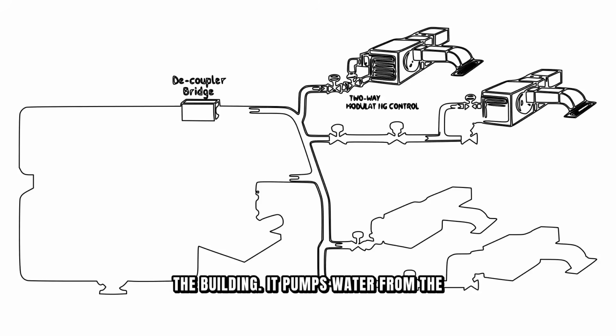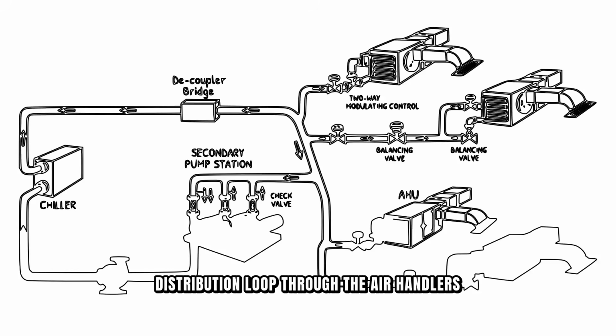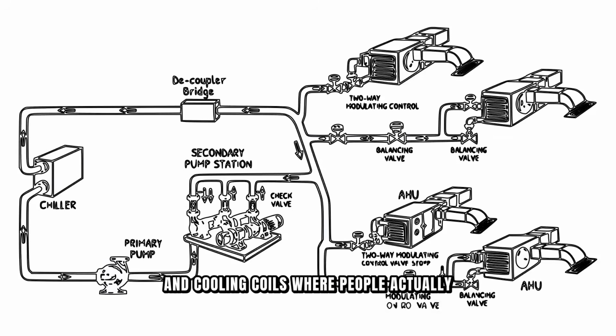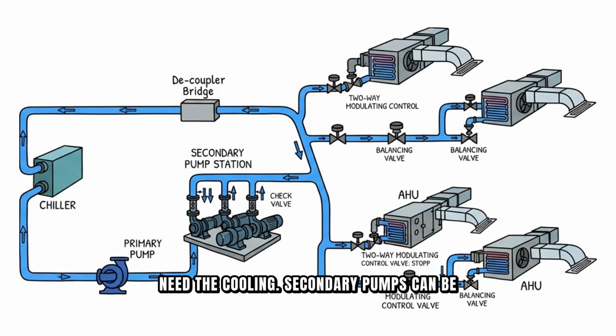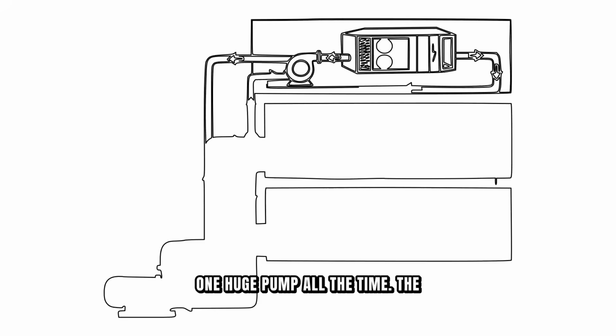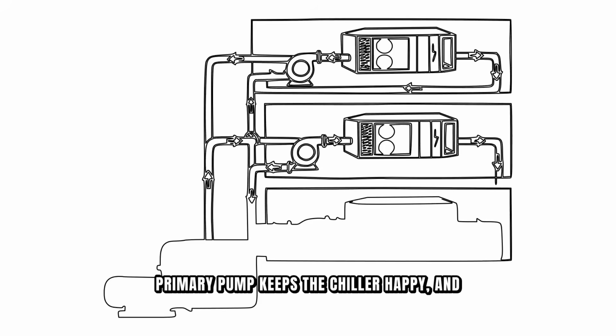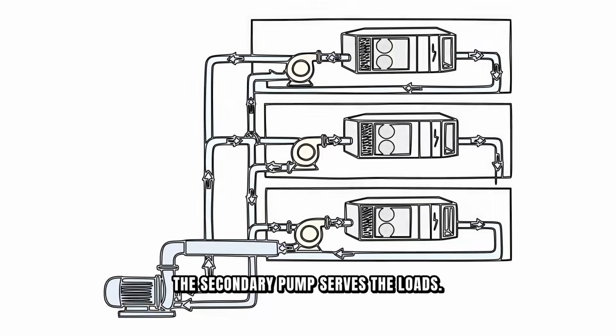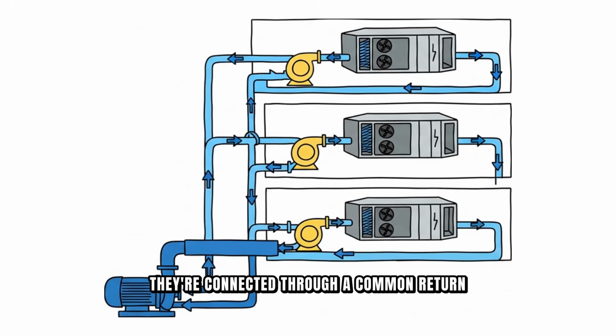The secondary pump is what actually serves the building. It pumps water from the distribution loop through the air handlers and cooling coils where people actually need the cooling. Secondary pumps can be turned on and off or modulated based on demand. This is much more efficient than running one huge pump all the time. The primary pump keeps the chiller happy, and the secondary pump serves the loads. They're connected through a common return line, so they work together as a system.